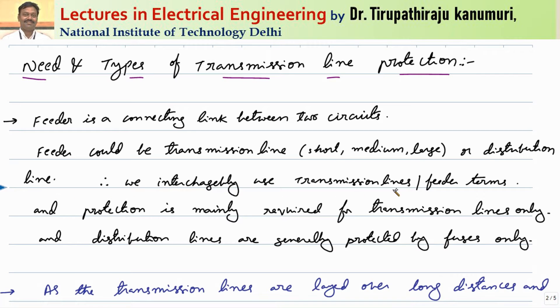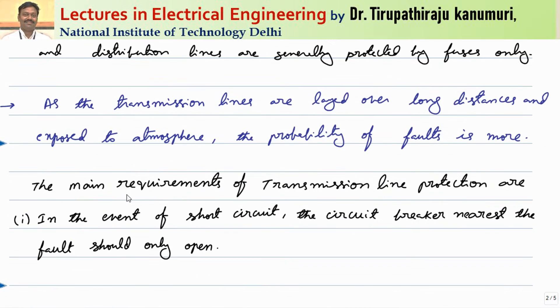That is why we interchangeably use the transmission line and feeder terms. Distribution lines are also called feeders, but generally protection for distribution lines is not done in the same way — they are protected by fuses only in most cases, due to economic concerns. Cost is a major concern for distribution lines and stability is not a major factor. Protection is mainly done for transmission lines and primary distribution, which we can also call transmission lines.